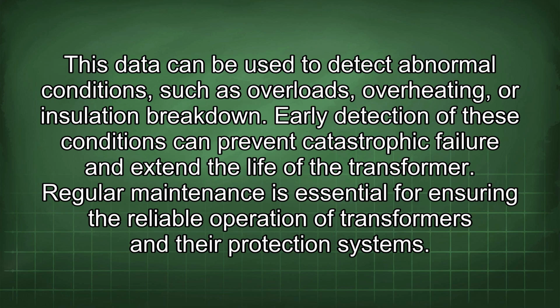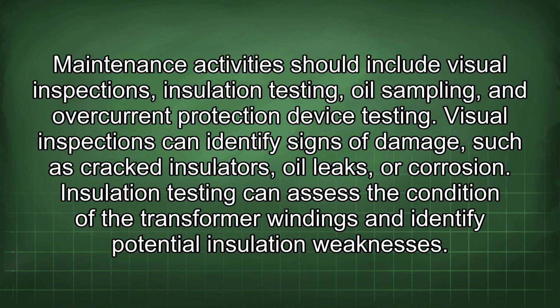Regular maintenance is essential for ensuring the reliable operation of transformers and their protection systems. Maintenance activities should include visual inspections, insulation testing, oil sampling, and overcurrent protection device testing. Visual inspections can identify signs of damage such as cracked insulators, oil leaks, or corrosion.